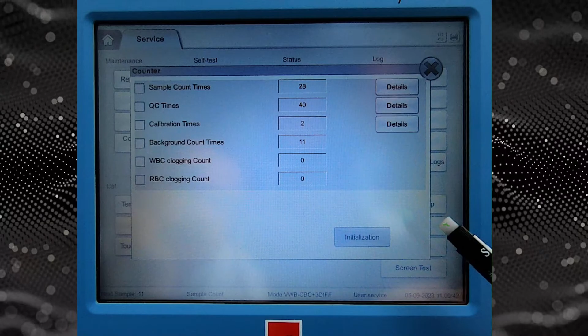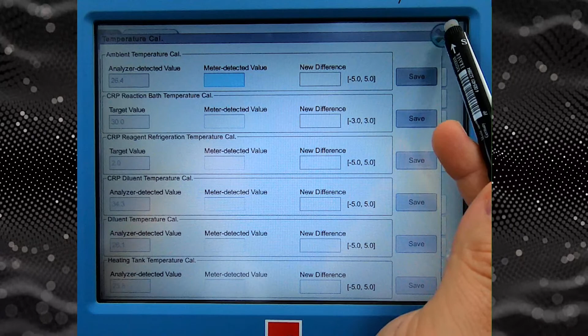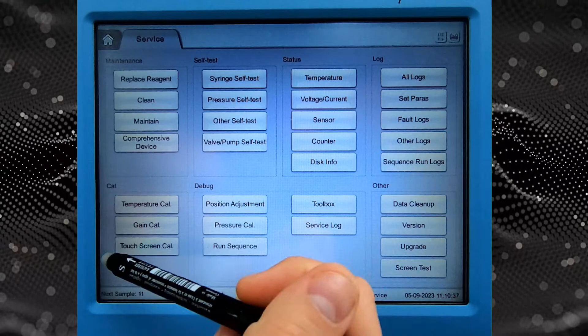It can be useful, but I believe there will be no need to make any adjustments here. But this menu allows you to basically adjust the reading from the temperature sensor. So, ambient temperature calibration, or ambient temperature sensor. This sensor, which is built into the analyzer, shows you 26.4, and you know that in your room right now it is 21, not this. So you can type minus 5, for example, and the analyzer will make this adjustment for you.